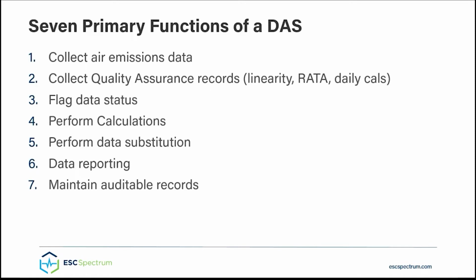These records are used to measure the validity and accuracy of the data collected. Third, the DAS flags data to indicate whether it's valid and in control based on regulatory requirements. Fourth, it performs calculations including generation of the required averaging intervals and some reporting parameters. And fifth, the DAS performs data substitution. This involves substitution of computer-generated values for periods where there is no valid CEMS data available.